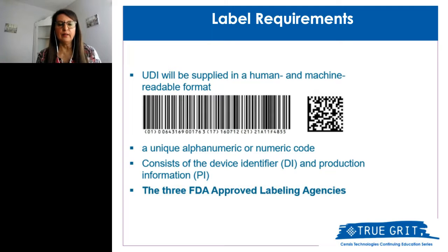So you can see here we have the DI and the PI, and this is called a linear barcode, and this here is called a 2D matrix barcode. I'll take this minute to point out that a linear barcode reader cannot read a 2D barcode. And a lot of the manufacturers are going to 2D because it's a much smaller piece of landscape on that labeling. So you have to make sure that you've got a barcode scanner that can read both 2D and the linear barcode.